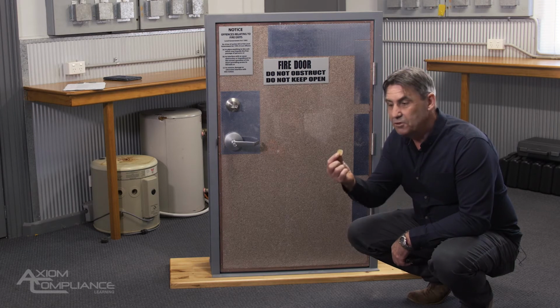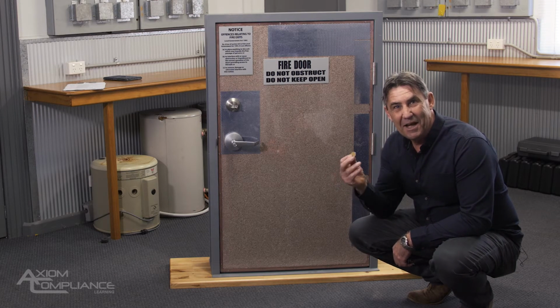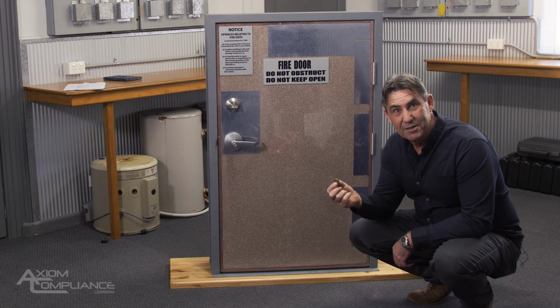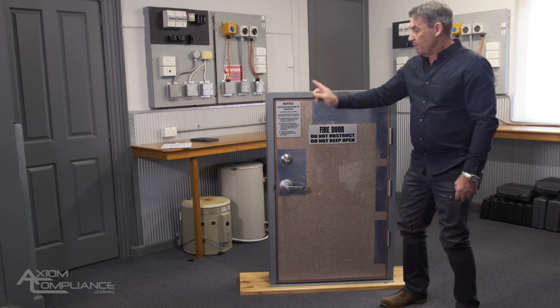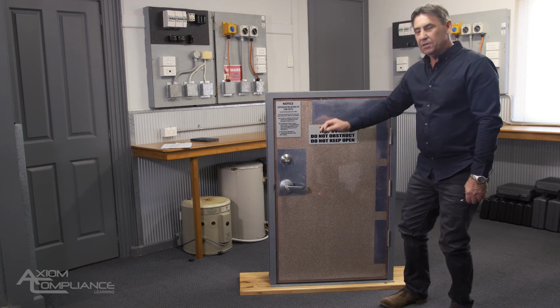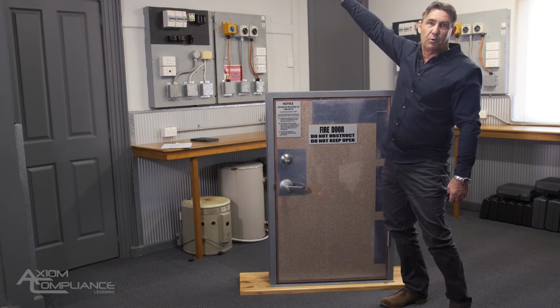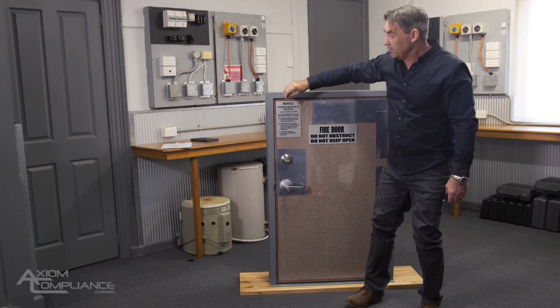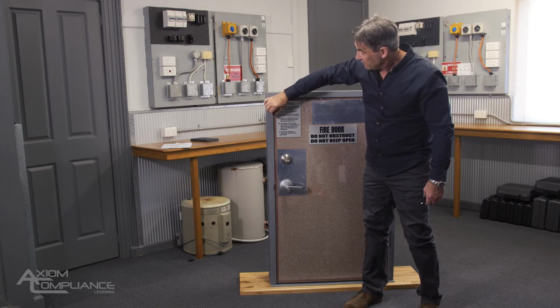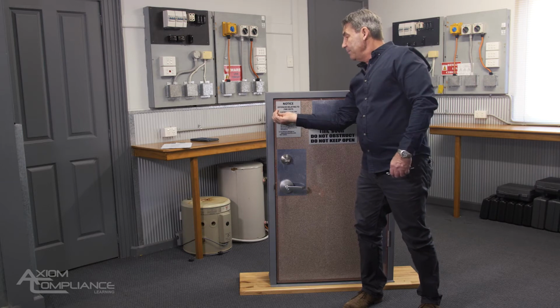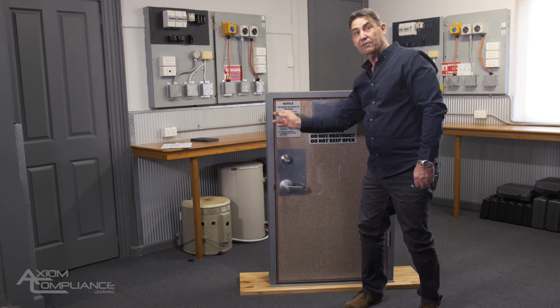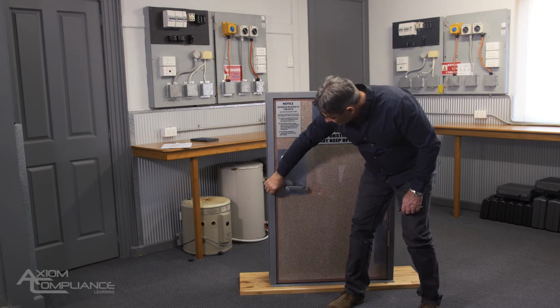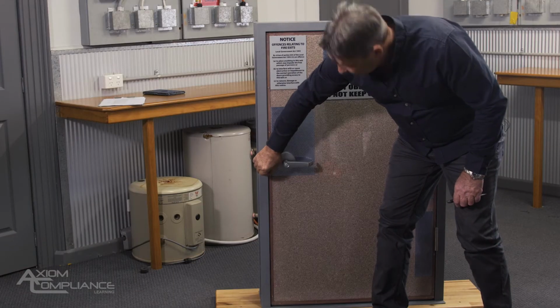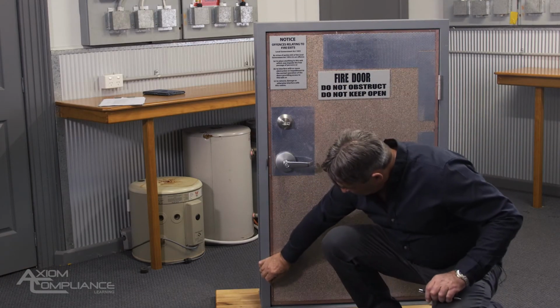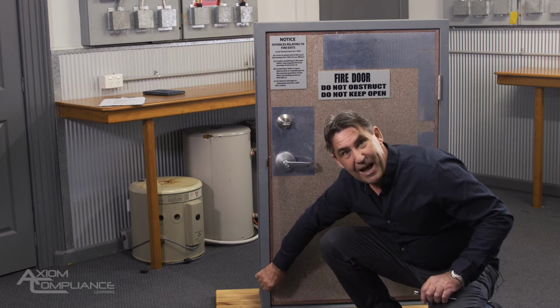I'm pretty miserable, so I just use coins. A $1 coin is around about 3 millimeters. In fact, it's exactly 3 millimeters thick. So remember, this is only a half-size door. If you had a full door at 2.1 meters, you would need to check in 3 places, 750 millimeters apart. So up here, I don't know whether you can see it, but it's very tight. In the middle of the door, it's still quite tight. I can't get my coin in there. And at the bottom of the door, I can just start to get my coin in there.